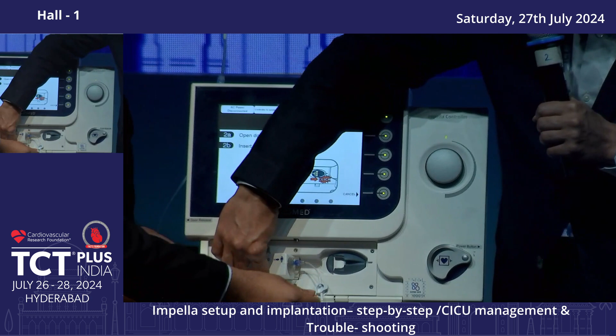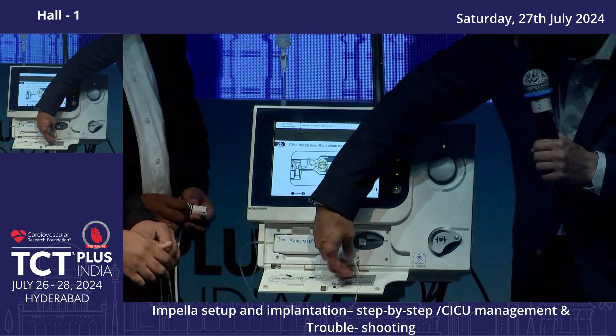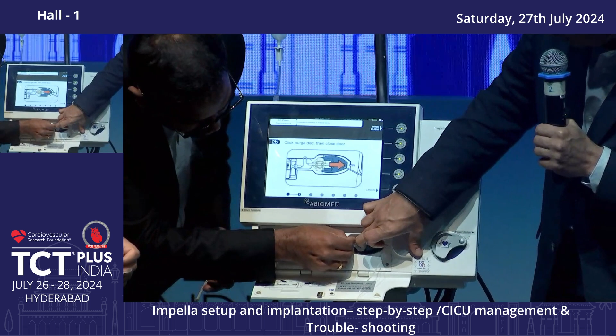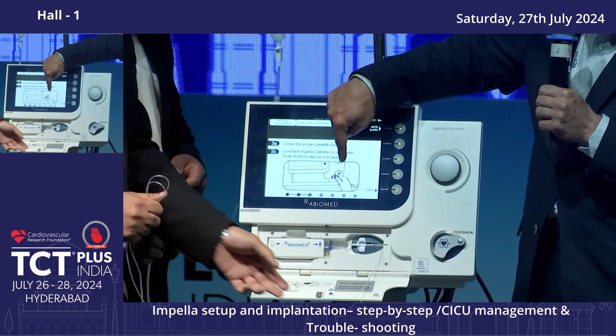The next thing it tells you to do is insert the purge cassette. So you do this with the Abiomed label on the outside. There's only one way to fit it in. Once you fit that in, you take the second segment and you fit it into this slot, okay? And pull it, there you can just fit that, and just push it in until it clicks. That's exactly what it tells you to do here. Okay, and now it starts to prime the system.